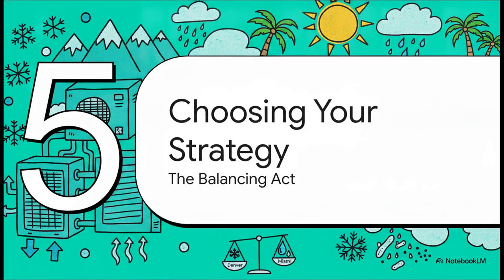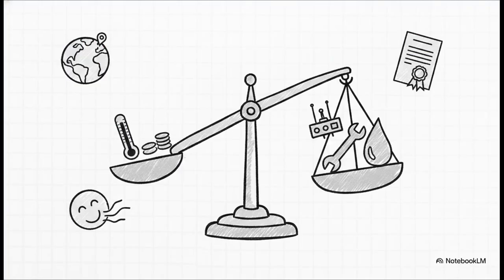So, wrapping things up with Section 5, choosing your climate strategy. It really is a massive balancing act. As you can probably guess by now, there is no magic bullet here. There's no universal best strategy, because what saves you thousands of dollars in Denver could cause an absolute mold catastrophe in Miami. Designing a building's high-limit strategy is tough. Engineers have to perform incredibly rigorous site-specific analyses. They've got to weigh the climate zones, strictly adhere to those ASHRAE 90.1 energy standards, and balance the cheap upfront costs of dry bulb systems against the humidity-taming but high-maintenance enthalpy systems, all while making sure the indoor air quality remains safe and comfortable for everybody inside.